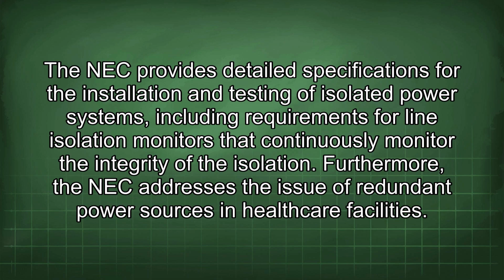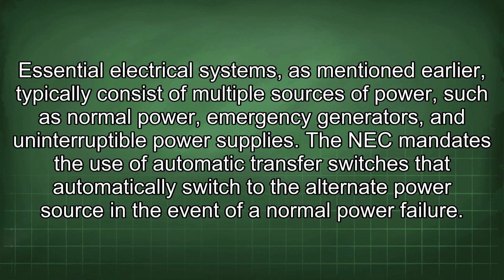Furthermore, the NEC addresses redundant power sources in healthcare facilities. Essential electrical systems typically consist of multiple sources of power, such as normal power, emergency generators, and uninterruptible power supplies. The NEC mandates the use of automatic transfer switches that automatically switch to the alternate power source in the event of a normal power failure.